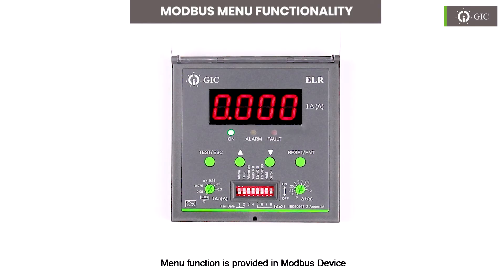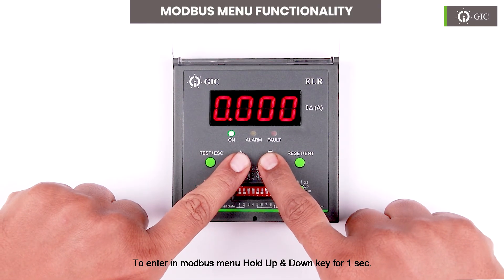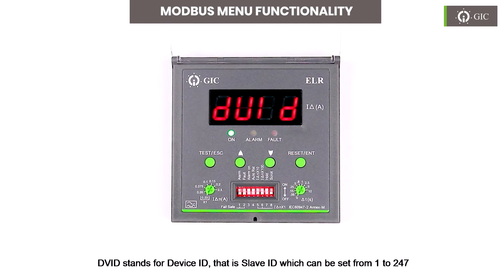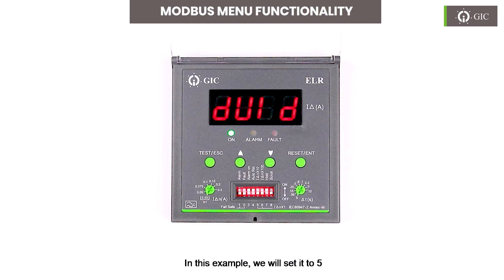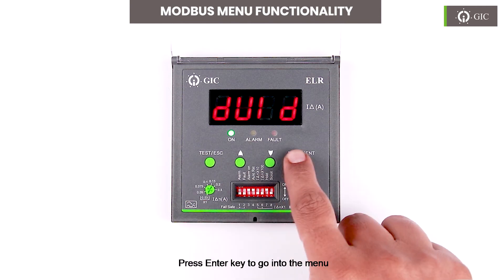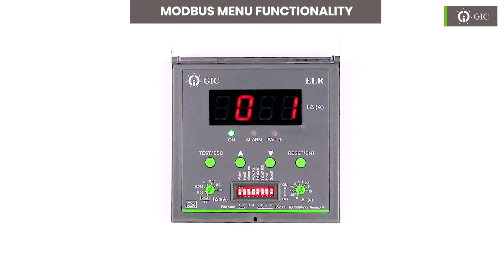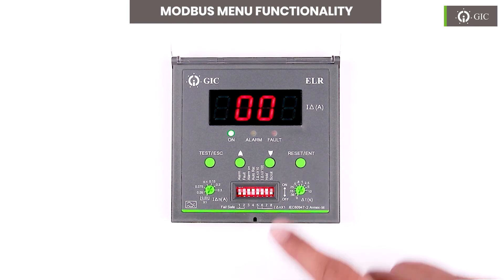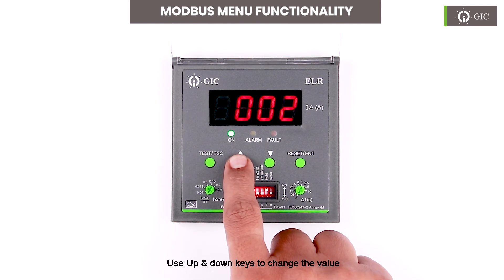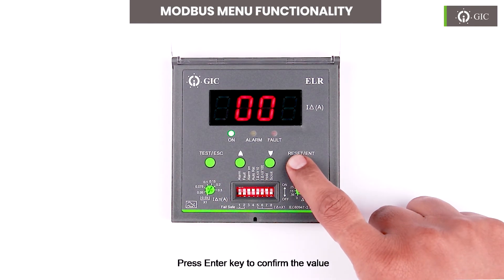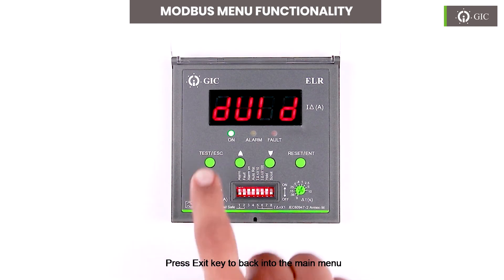Menu function is provided in the Modbus device. To enter the Modbus menu, hold the Up and Down keys for 1 second. COMS stands for communication setting. DVID stands for device ID, that is slave ID, which can be set from 1 to 247. In this example, we will set it to 5. Press the Enter key to go into the menu, then press Enter again to start changing the value. Use the Enter key to select the desired digit, use the Up and Down keys to change the value, press Enter to confirm, and press the Exit key to go back to the main menu.